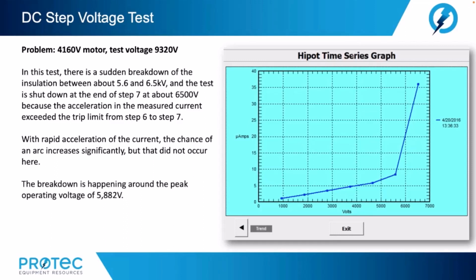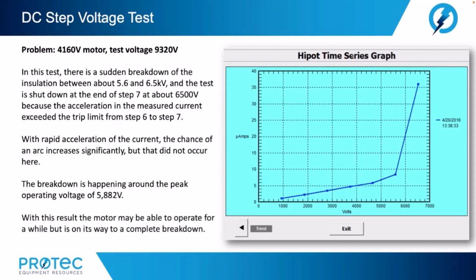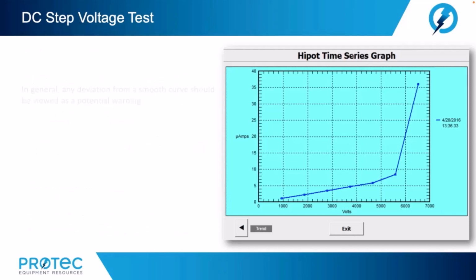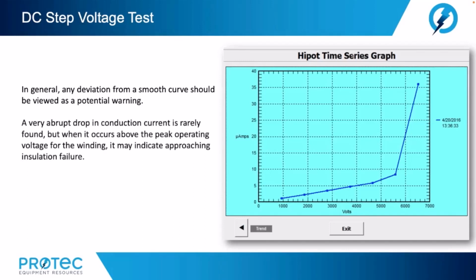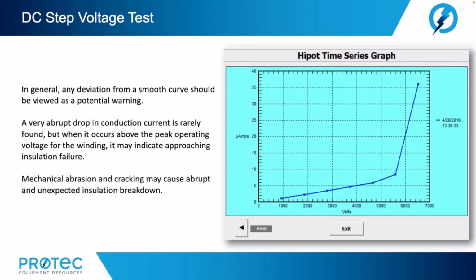The breakdown is happening around the peak operating voltage of 5,882 volts. With this result, the motor may be able to operate for a while, but it is on its way to a complete breakdown. In general, any deviation from a smooth curve should be viewed as a potential warning. A very abrupt drop in conduction current is rarely found, but when it occurs above the peak operating voltage for the winding, it may indicate approaching insulation failure. Mechanical abrasion and cracking may cause abrupt and unexpected insulation breakdown.